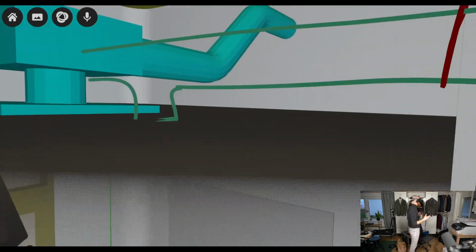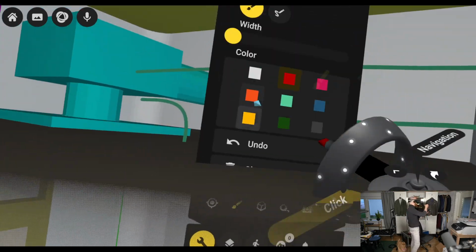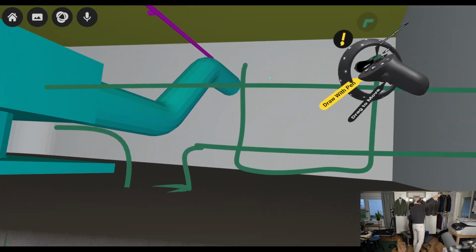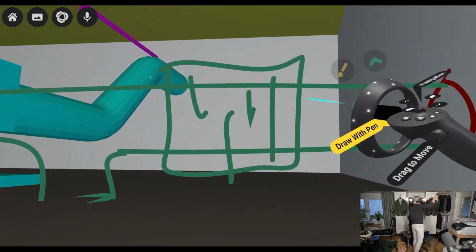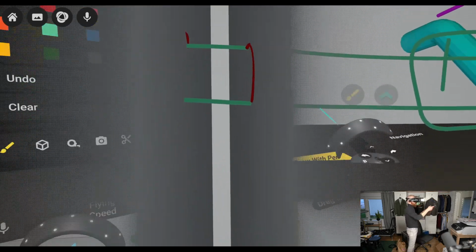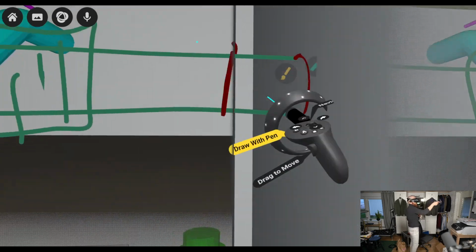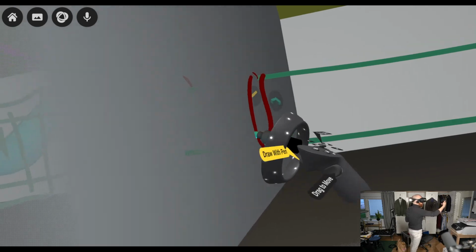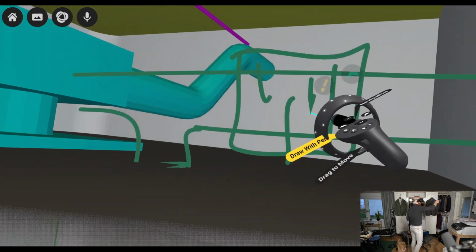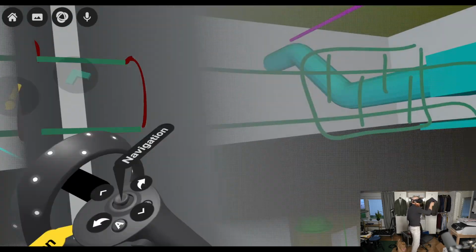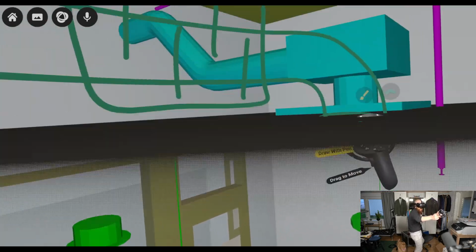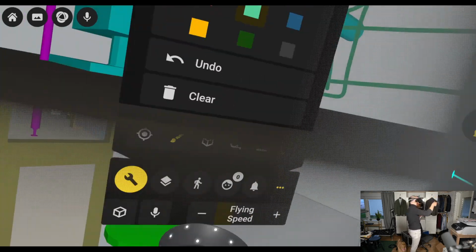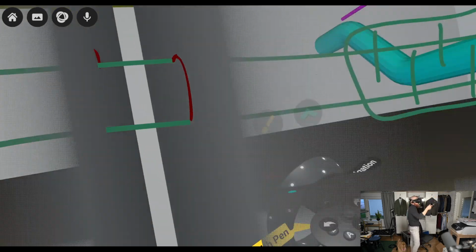But we are not there yet, because you also have to remember that there's something called break-in and break-out transmission. Even though we put a silencer, for the sake of it, we put another one here. We are paranoid. We have silencers on both sides now of this one. But you see here we have exposed ventilation duct. So even though this ceiling is airtight, and we have silencers on both sides on the openings, this surface remains exposed. So what can happen is so-called break-in and break-out transmission.